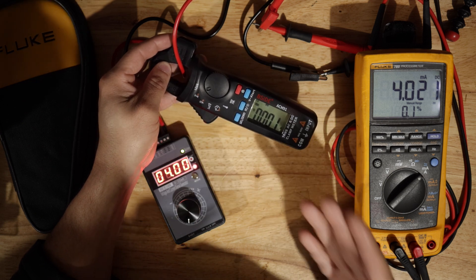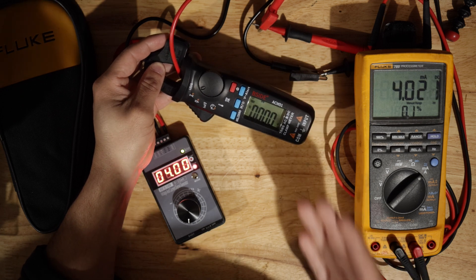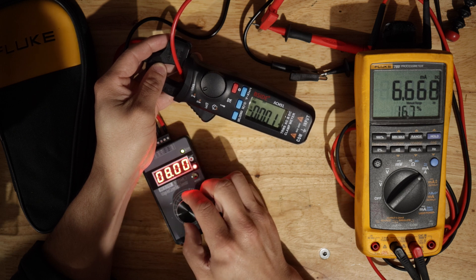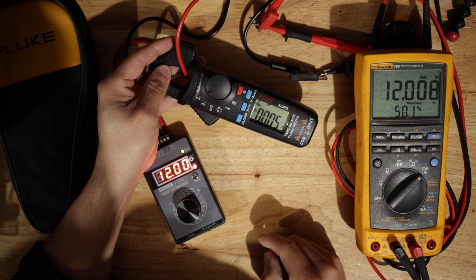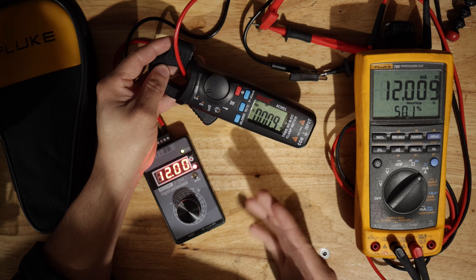They say it's supposed to be accurate down to 1 mA, so I expect 1 mA accuracy. Let's go 50%, which is 12 mA. And this is what I got — 9.5.